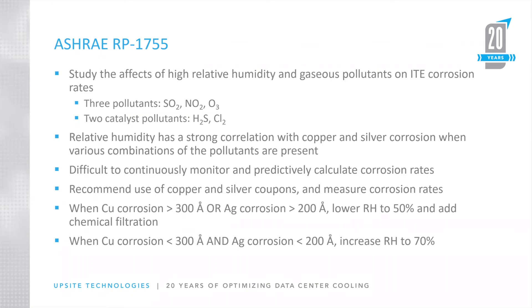Any time you see a copper corrosion rate in excess of 300 angstroms or silver in excess of 200 angstroms, the best way to cut down on that corrosion rate is to lower the relative humidity to 50% and add some chemical filtration — maybe some carbon scrubbers — to take some of those pollutants out of the airstream.